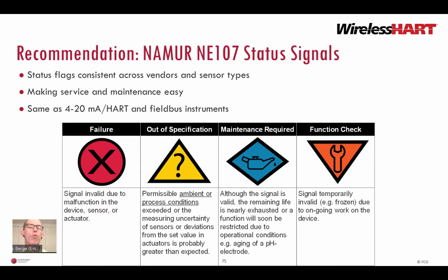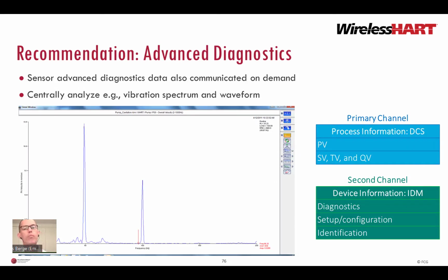WirelessHART solves this by supporting the NAMUR NE107 recommendation for 4 standard status signals. Sensor health is mapped to these 4 status signals. As a result, status display becomes consistent across vendors and sensor types, making service and maintenance easy. Many I&C engineers are already familiar with the NE107 status symbols, so they will welcome this. Additionally, WirelessHART provides advanced diagnostics communicated by request response or client-server communication as a non-real-time, second channel. This enables you to centrally analyze advanced diagnostics such as retrieving spectrum and waveform from a vibration transmitter.